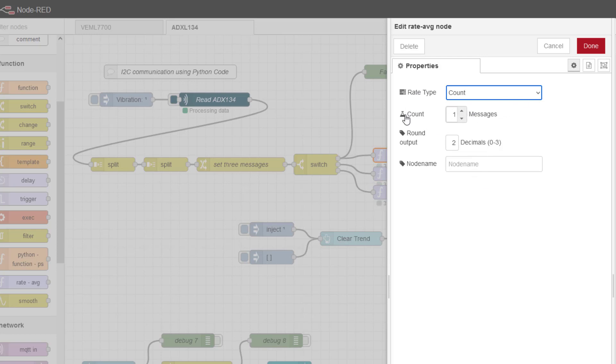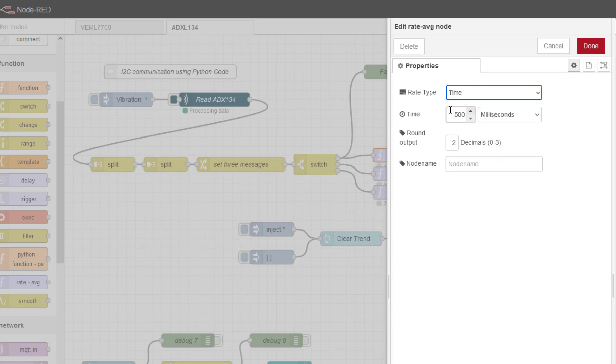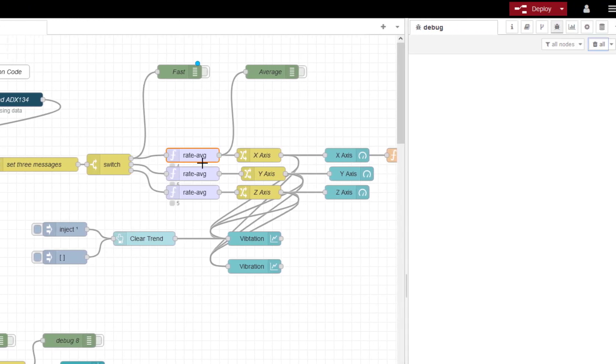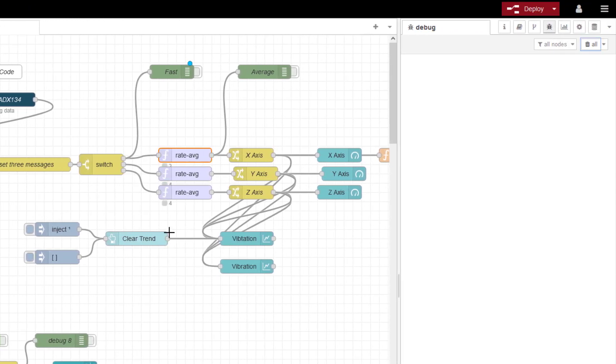This is 100 milliseconds update time I believe. So if we did 10 that would be the equivalent to one second or we can just do it on time. So we're doing 500 milliseconds and then you'll get one value out which is the average of all those process values every 500 milliseconds to two decimal places. We've deployed that already.